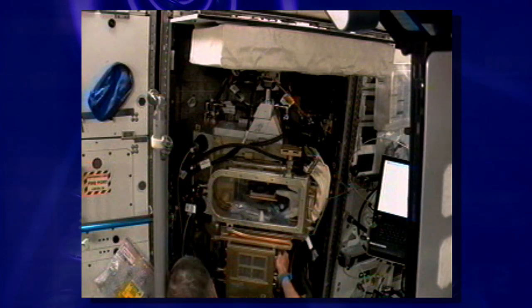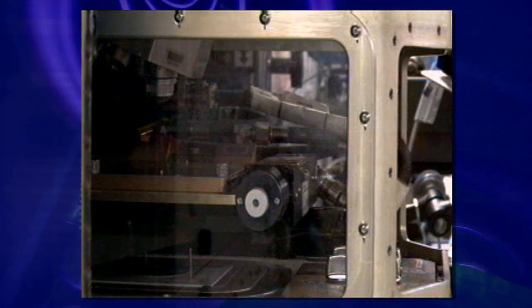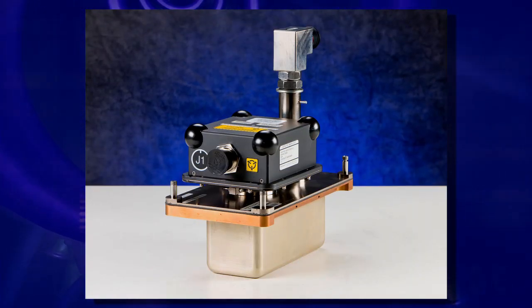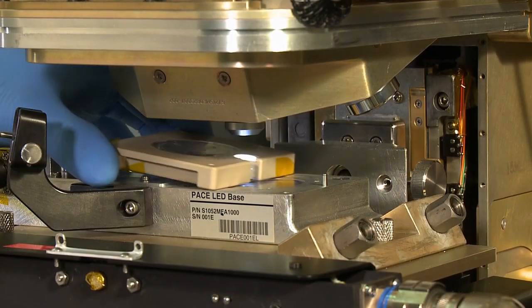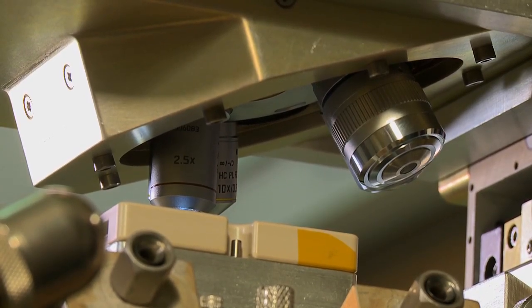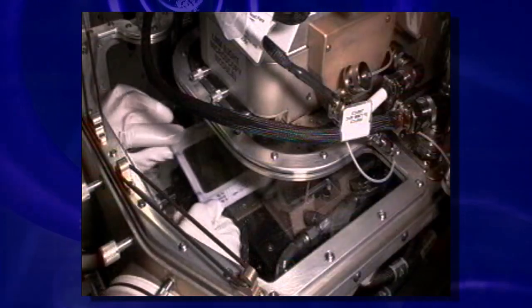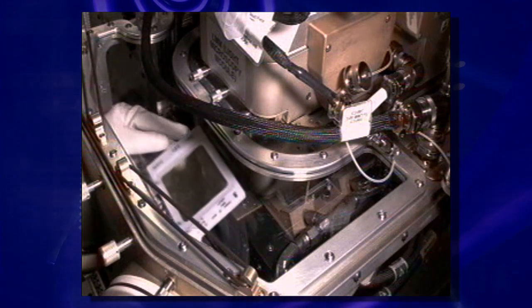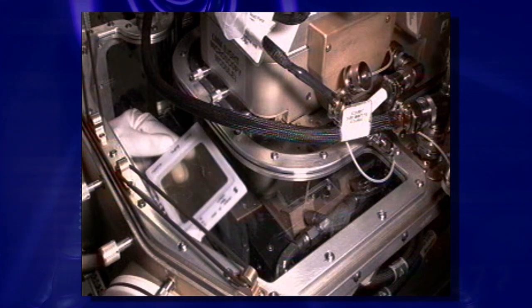Inside the auxiliary fluids container, the experiment sample is always moved relative to the fixed objective lens of the microscope. Motors on the translation stage assembly and in the body of the microscope automate movement of the sample across the X-Y plane and along the main axis, or Z direction. The LMM can image regular and specially designed microscope slides containing colloids and can also view opti-cells, which provide oxygen transport through a membrane and containment for the biological sample and the sample medium.